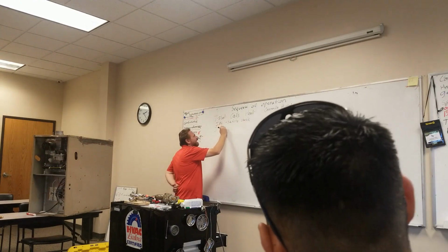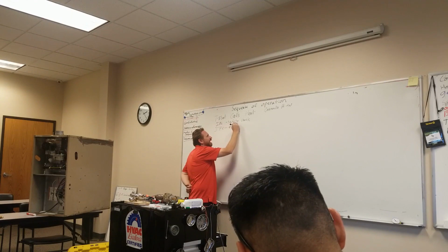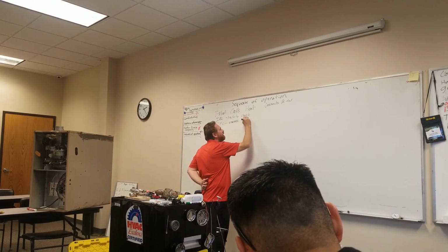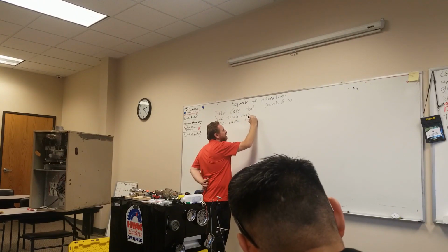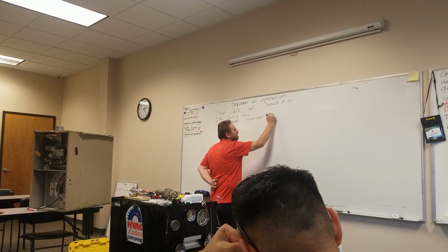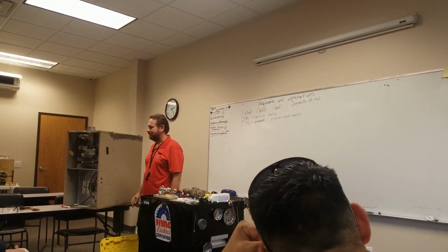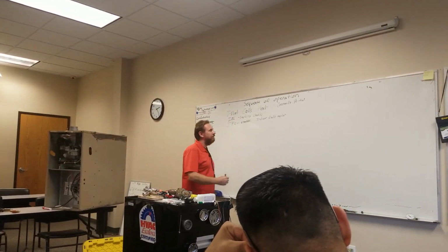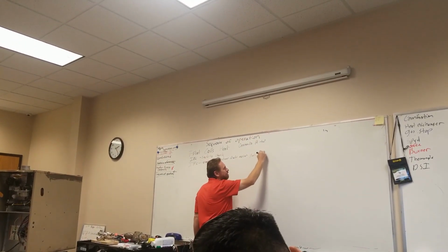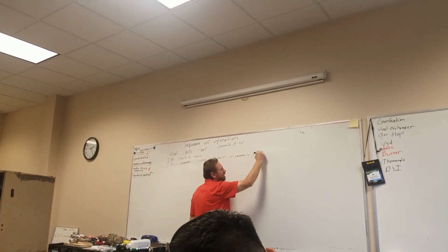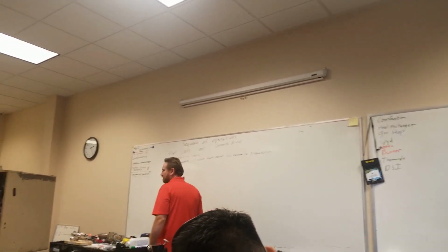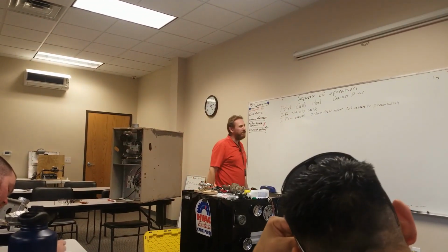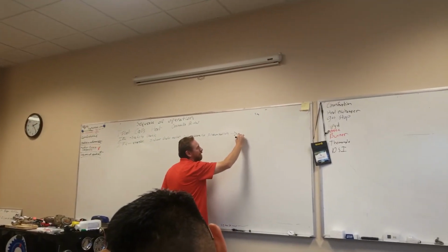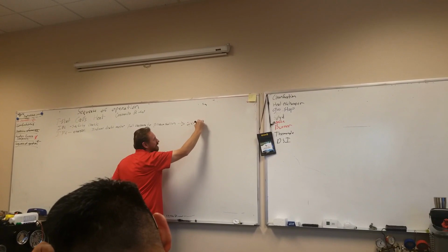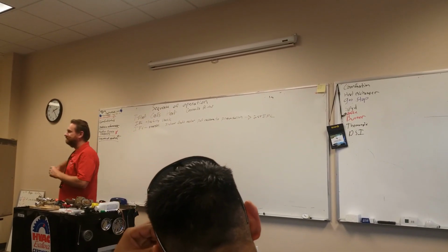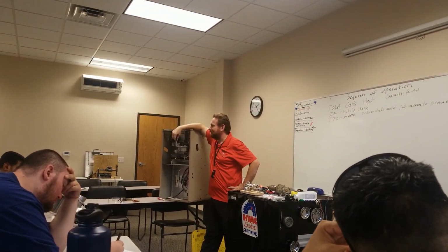Then the IFC is going to energize. By energize, I mean send voltage to the combustion motor or the inducer draft motor. That's going to pull a draft through the heat exchanger. It's also going to pull a vacuum to the pressure switch. That pressure switch is then going to tattletale, or send 24 volts to the IFC, to ensure that inducer fan motor is working. How great is that? Isn't that cool?